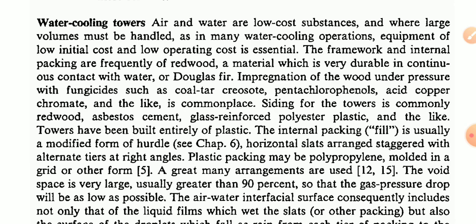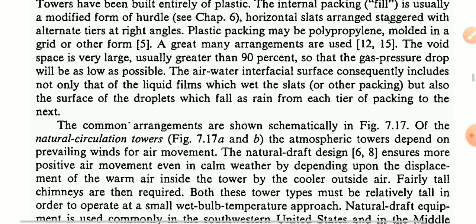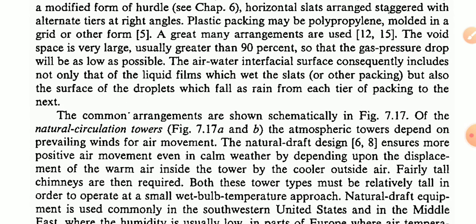Towers have been built entirely of plastic. The internal packing fill is usually modified from the hurdle type in this chapter, with horizontal slots arranging the stages, with alternate tiers at right angles. The plastic packing may be polypropylene molded in a grid or other form. A great many arrangements are used.